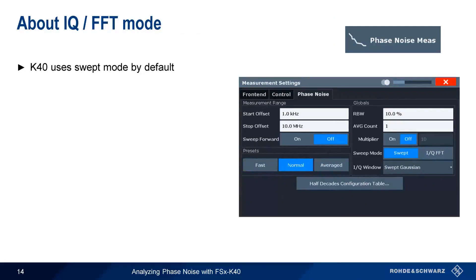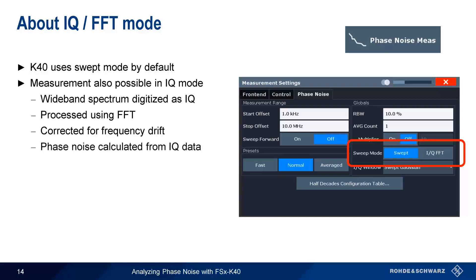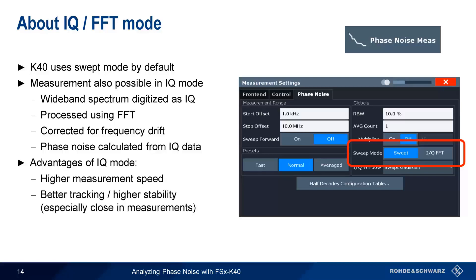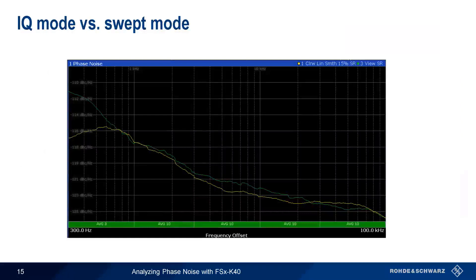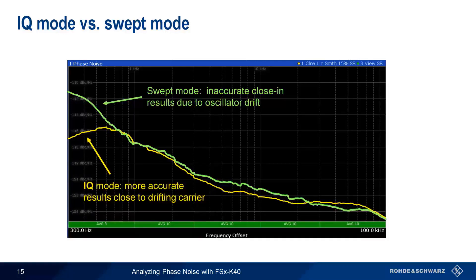By default, the K40 option uses the traditional swept analysis mode, but phase noise can also be measured using IQ mode. In this mode, wideband spectrum is acquired and digitized as IQ data — samples containing both magnitude and phase information — processed using the fast Fourier transform, corrected for frequency drift, and used to calculate phase noise results. IQ mode has several important advantages: it is usually several times faster than swept mode and provides better tracking and higher stability, especially for measurements close to the carrier. For example, when measuring a slightly unstable VCO, swept mode gives inaccurate results at close-in offsets due to oscillator drift, while IQ mode gives a more accurate result since drift can be corrected before phase noise is calculated.